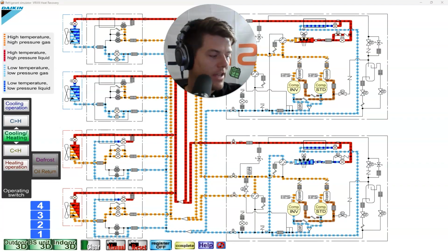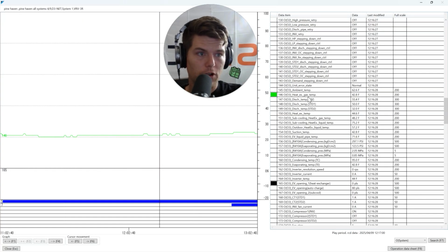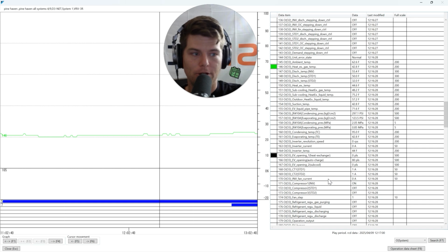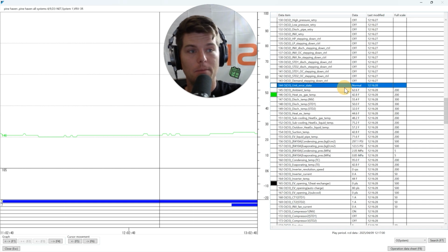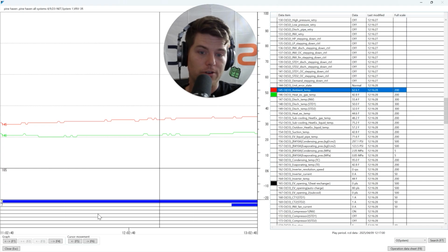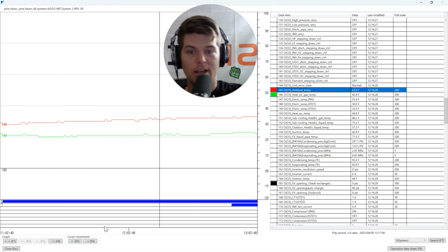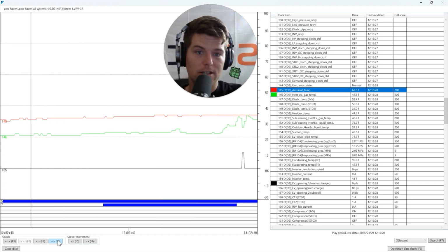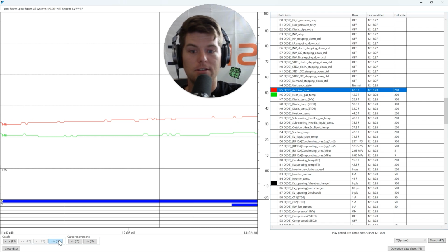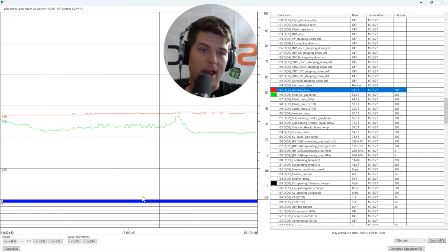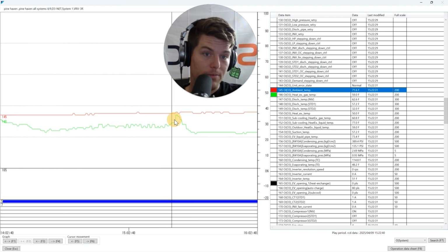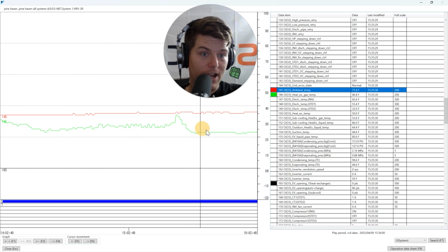How do we know if it's actually doing that? So we scroll up here, heat exchanger gas temp, make sure my fan is running. 1 step, there's some air moving across that coil. My ambient temperature is what? 62 degrees. With this being at 0 pulses and at 62 degrees, does it ever rise up to that temperature? And the answer is yes, only when it opens up 2,000 pulses. But look, it falls back down. So let's take a look at that too. You can see here where it goes up and then it comes back down again.